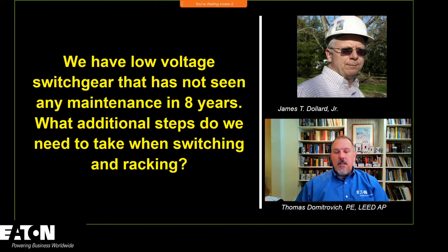that doesn't seem right. So the change we did in 230 with regard to modifying the 6 disconnect rule, we didn't get rid of the 6 disconnect rule. We simply said you need to have barriers around each of those main overcurrent devices. You're never going to see six circuit breakers or 6 breakers in a panel board for service entrance equipment. You're going to have to break those out as one panel with a main or 6 separate disconnects feeding sub panels, and that really addresses a safety concern from a design perspective. That's a great practice to have, is to sit down and say you're going to change your design a little bit to make things a little safer, and that's sort of what we did for those service entrance equipment. So I think that was a really big step forward.